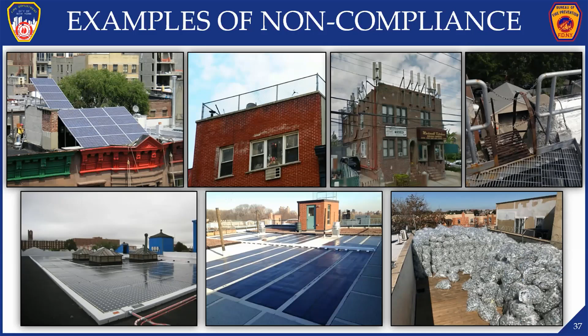There are also concerns about whether the panel is damaged, or whether heat is damaging them from below. Firefighters don't know the safety condition of your panels, and they don't have time to look at signs and verify it. They have a job to do while they're up there. So the assumption is: never step on panels, never step on glass. They will not step on them, and therefore we consider them obstructions to the clear path. In these two pictures, while it looks very clean and open, these arrays actually obstruct the clear paths and clearances of the things they surround.